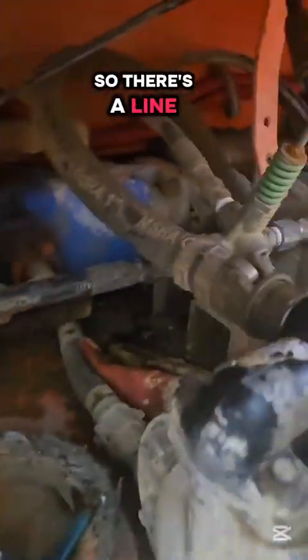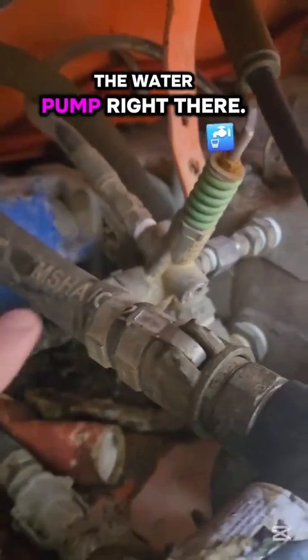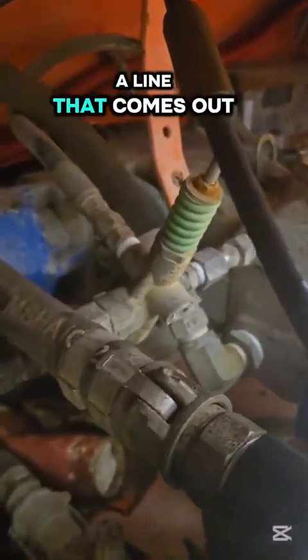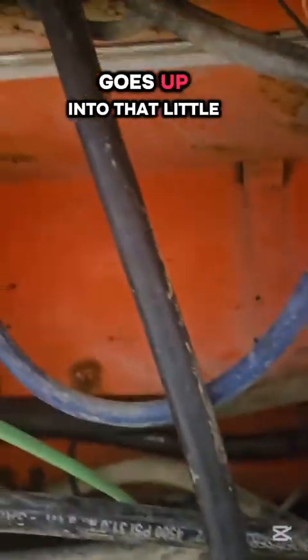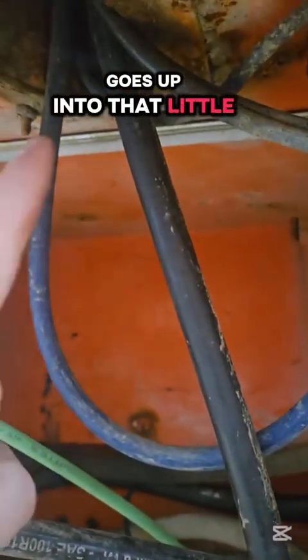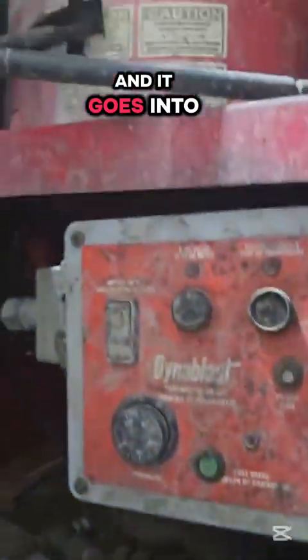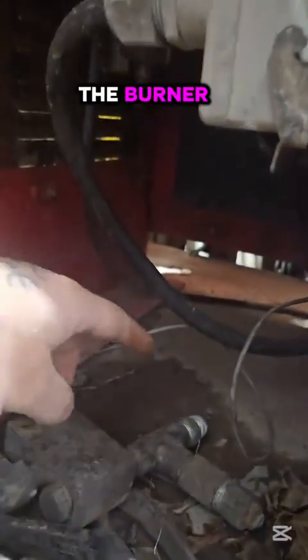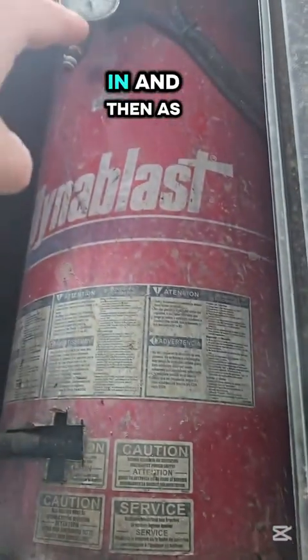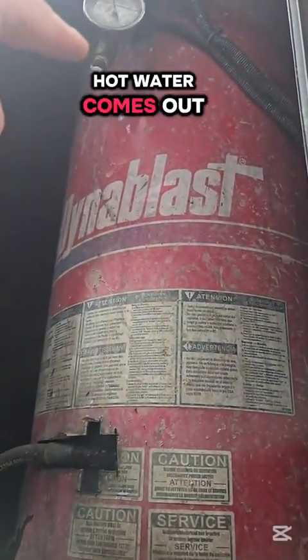Let me show you what actually went on here, so that maybe I can spare it from happening to you. So there's a line that comes out of the water pump, right there, there's the unloader, there's a line that comes out of it, goes up into that little hole there, and it goes into the bottom end of the burner. So it goes into the flow sensor, comes out, goes up, sends the cold water in, and then as it heats it, the hot water comes out of there.